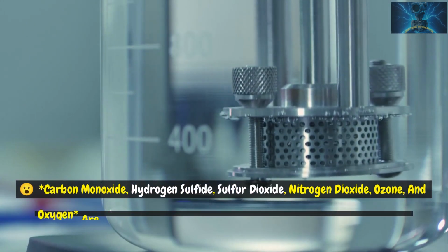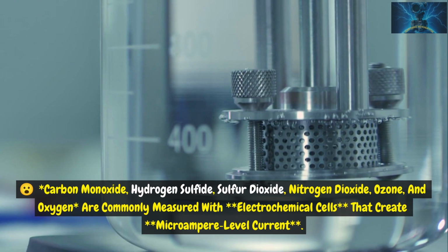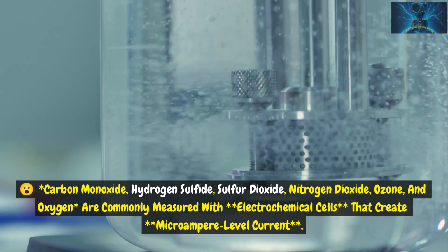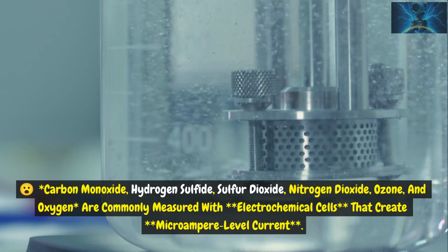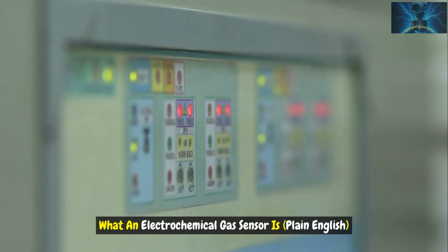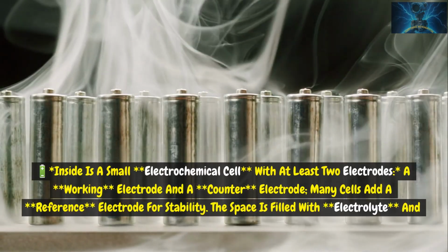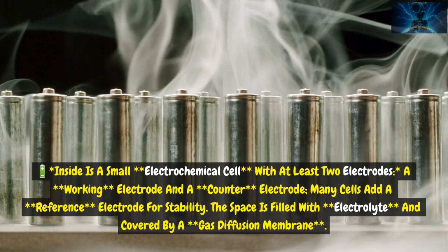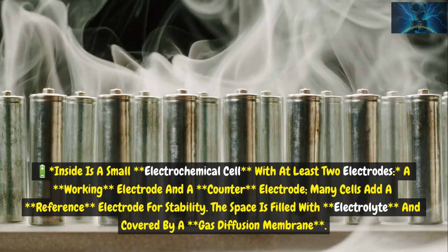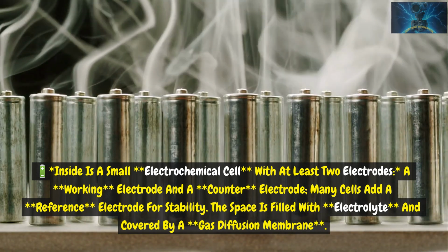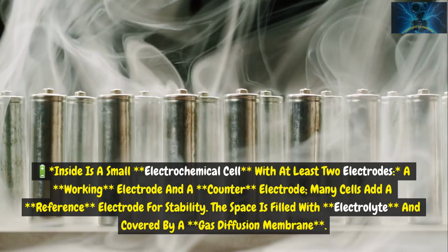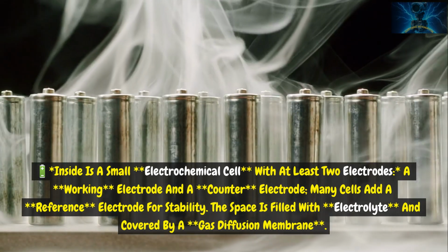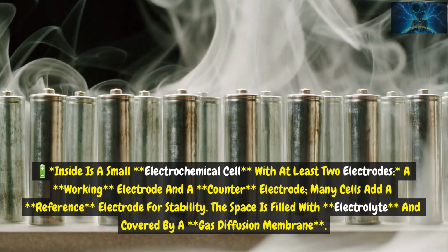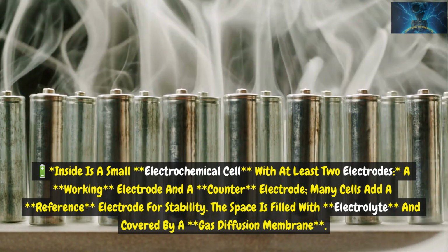Carbon monoxide, hydrogen sulfide, sulfur dioxide, nitrogen dioxide, ozone, and oxygen are commonly measured with electrochemical cells that create microampere level current. What an electrochemical gas sensor is, plain English. Inside is a small electrochemical cell with at least 2 electrodes, a working electrode and a counter electrode. Many cells add a reference electrode for stability. The space is filled with electrolyte and covered by a gas diffusion membrane.